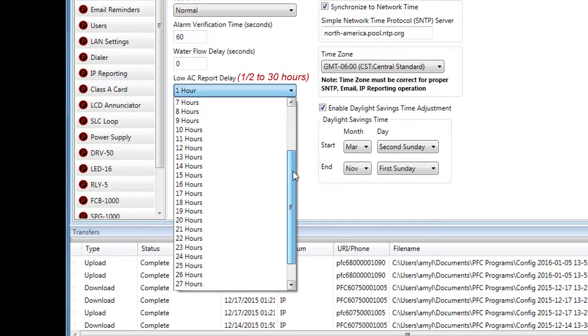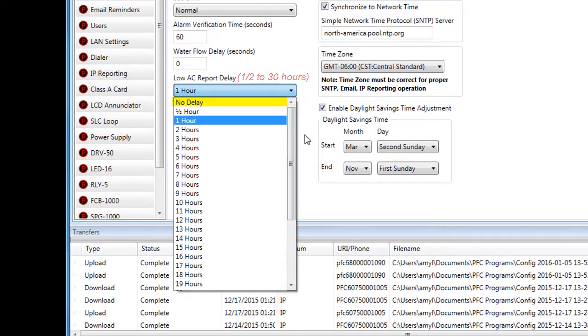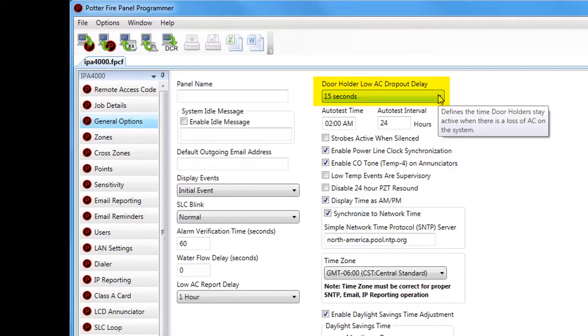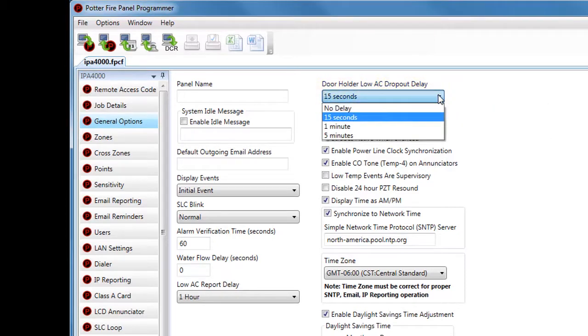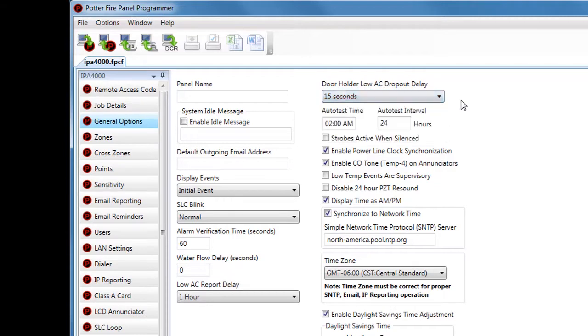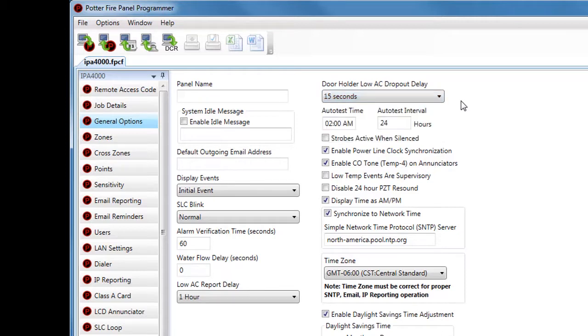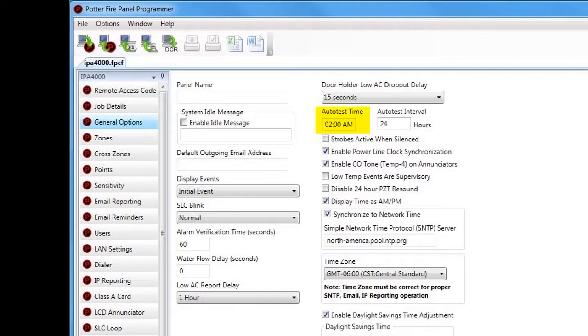By clicking the dropdown for AC Report Delay, you can select anywhere from half an hour to 30 hours, or select No Delay — in which case the trouble signal will send immediately on loss of AC. Moving to the next column, the Door Holder Low AC Drop Out Delay defaults to 15 seconds; options include No Delay, 15 seconds, 1 minute, and 5 minutes. A NAC circuit can be programmed as a Door Holder Low AC Drop Out, holding door holders open for the programmed time period during an AC loss — for example, to bridge the gap between AC loss and generator start-up.